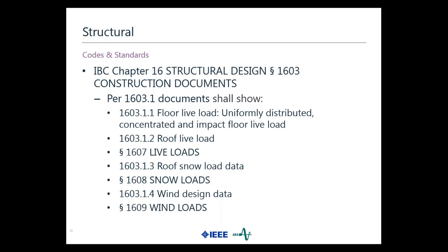That's why I've got this one specifically called out. The situation wasn't an electrical room per se - we were looking at running cable tray for a solar photovoltaic installation. Instead of going underground, they were looking at using cable tray for the distribution. I saw in one of the cable tray design manuals that you might need to consider snow load. I got with my CSA counterpart, and he confirmed it. Believe it or not, the snow load for that tray was actually 1.5 times greater than the medium voltage cable that was going to be in that tray.